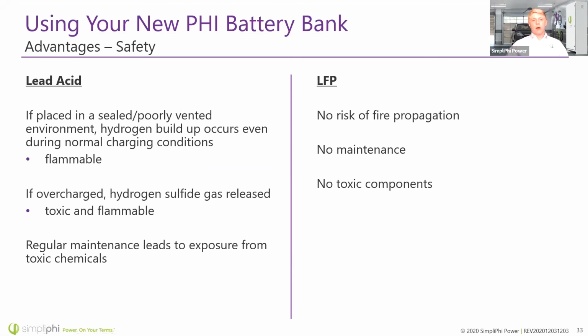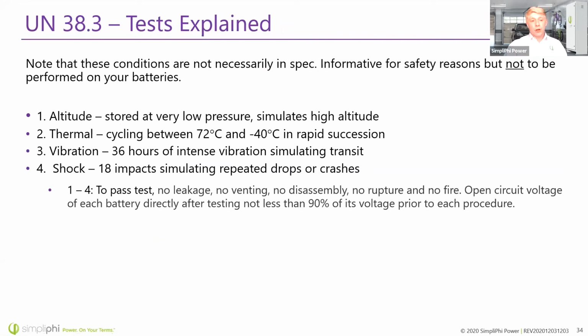Now, additionally, we've already talked about many of the safety benefits of switching your lead acid batteries to Phi, but just noting that there's no risk of fire propagation and no maintenance which would expose you to toxic components. To reassure you that our batteries are extremely safe, we have put them through so much testing. Third-party testing I'm talking about here, not just our internal testing. This is UN 38.3 tests. This is the test that allows us to ship our batteries on airplanes. They've first passed the altitude test, being stored at low pressures, then thermal cycling, super high and super low temperatures for a long time, just rapidly cycling hot and cold, hot and cold. They've passed intense vibration simulations as well as shocks, so just being dropped, thrown at the ground. This is going to simulate a crash or an impact.